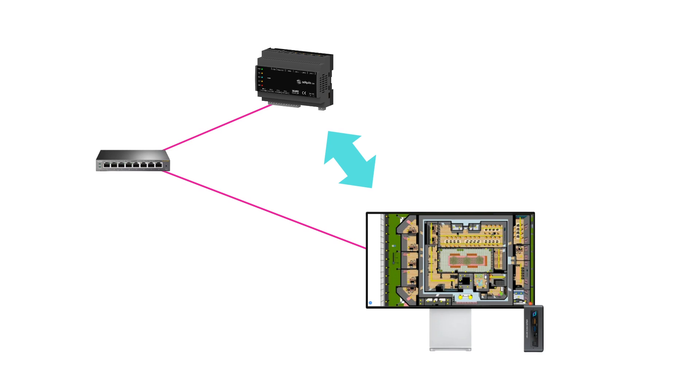One important thing to note before continuing is that you should try to export all Adkio variables to SCADA at once because each time you import them into SCADA, a new device will be generated. This is not a major issue since Adkio SCADA server supports any number of data sources and therefore any number of devices. However, to keep the information organized, it would be better if everything was under a single device.